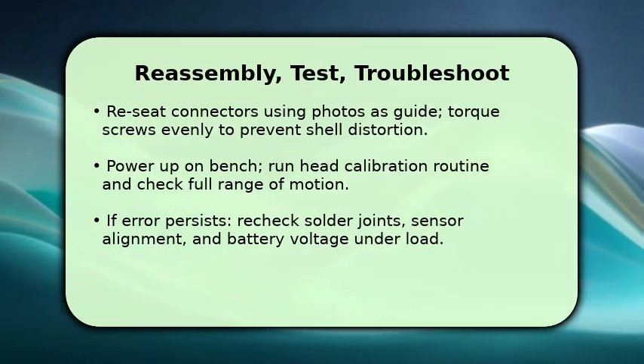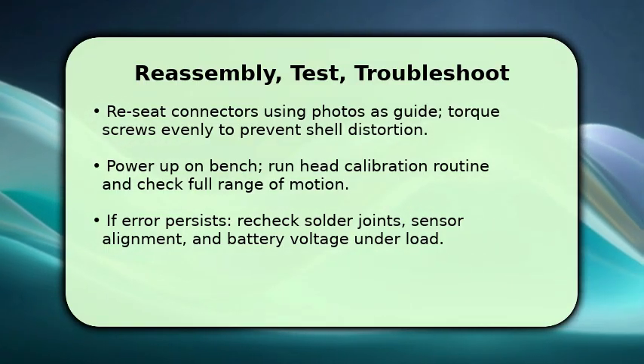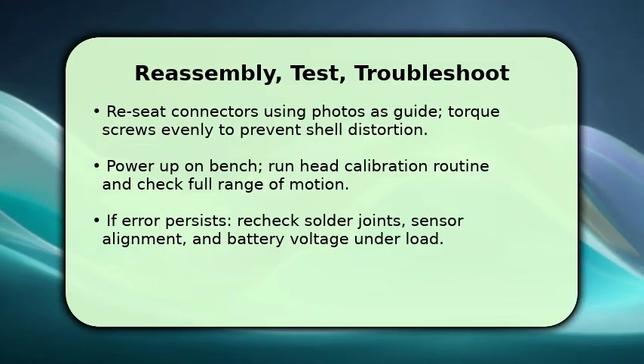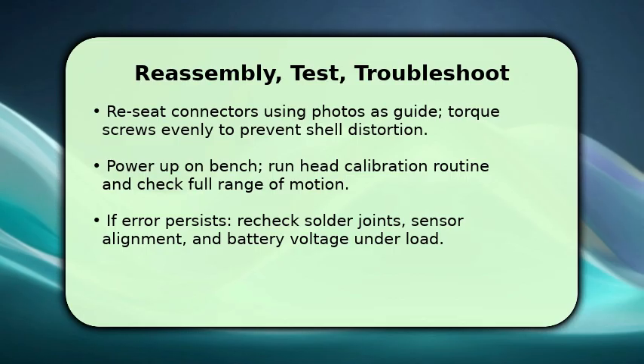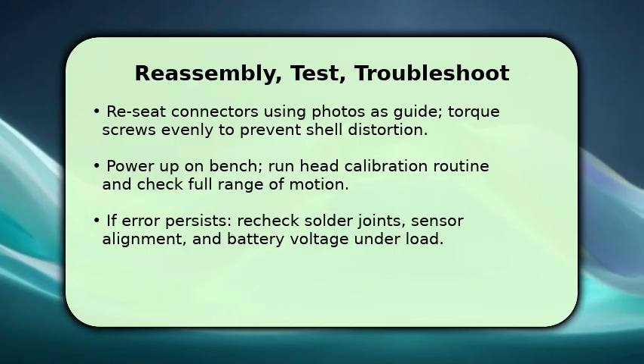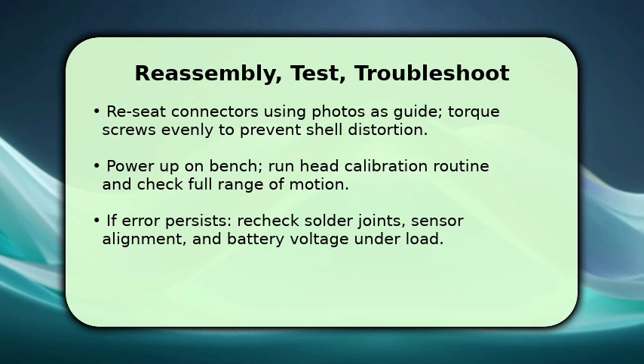If you still see errors, focus on one key troubleshooting tip: verify battery voltage under load and recheck any suspect solder joints or misaligned sensors before repeating calibration.